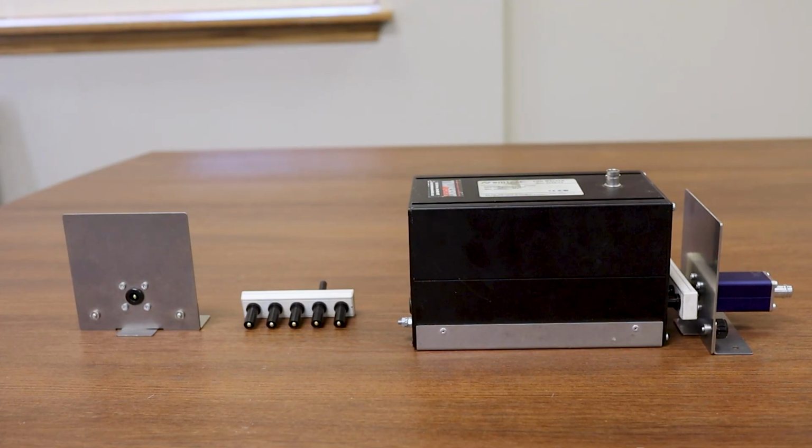This CDN is designed for testing three-phase equipment and would be connected to the input power going towards the equipment under test. The power input would be going into one side of the CDN and the output going towards the EUT connected to the other side. The connection on top will be going to the amplifier output on our NSG 4070, and we'll walk through more of that setup here shortly.